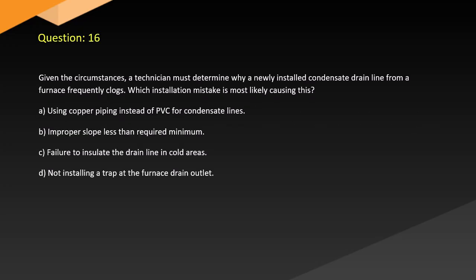Question 16. Given the circumstances, a technician must determine why a newly installed condensate drain line from a furnace frequently clogs. Which installation mistake is most likely causing this? A. Using copper piping instead of PVC for condensate lines. B. Improper slope less than required minimum. C. Failure to insulate the drain line in cold areas. D. Not installing a trap at the furnace drain outlet.